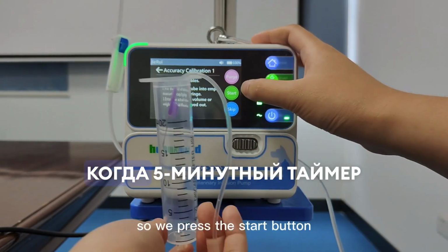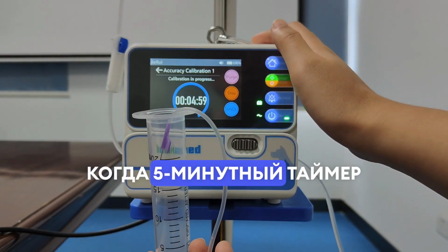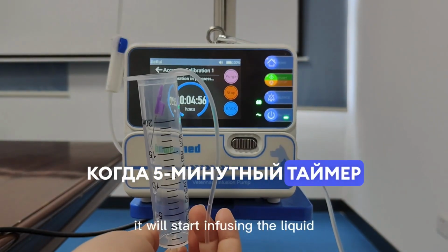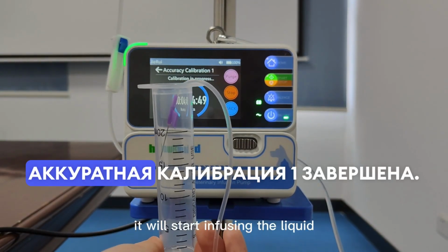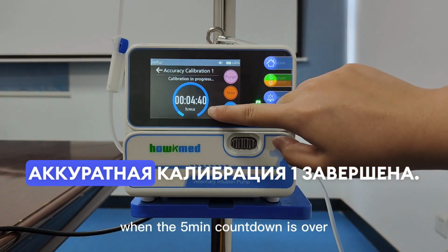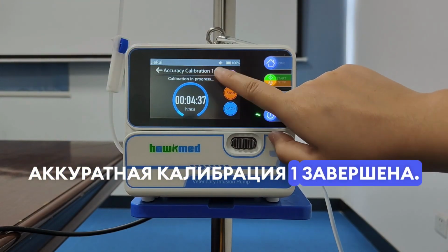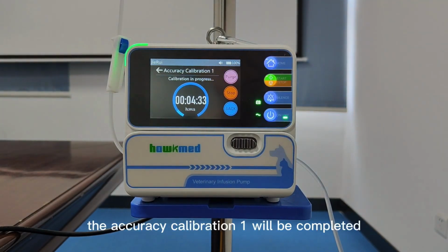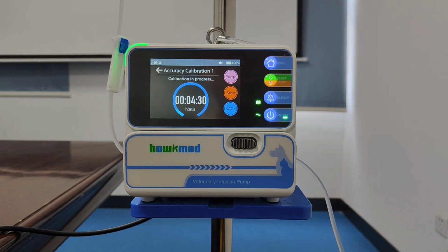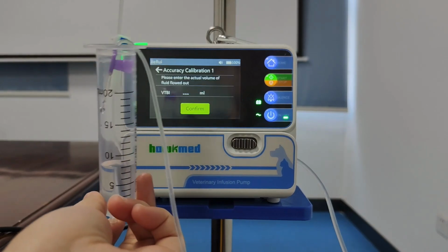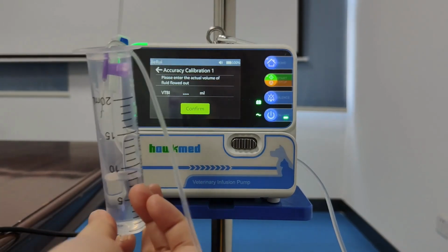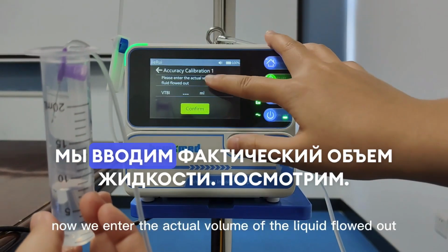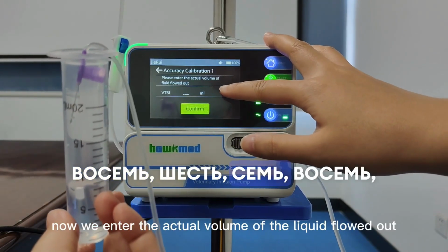So we press the start button. It will start infusing the liquid. When the 5 minute countdown is over, accuracy calibration 1 is completed. Now, we enter the actual volume of the liquid that flowed out.